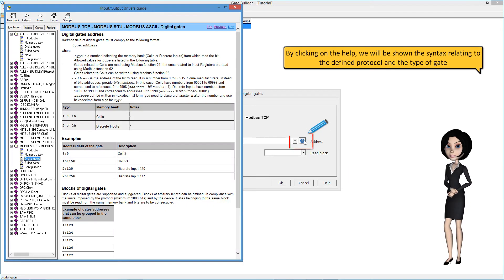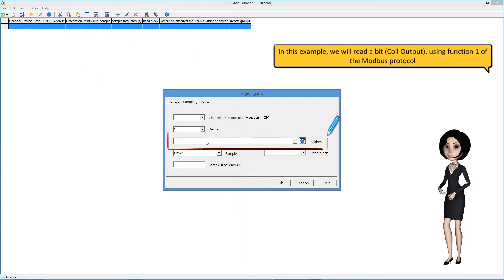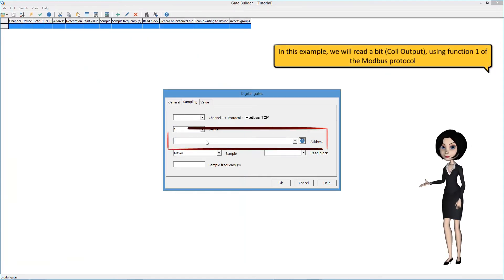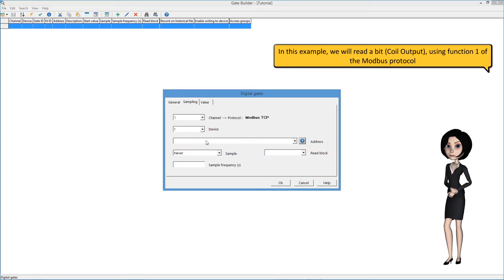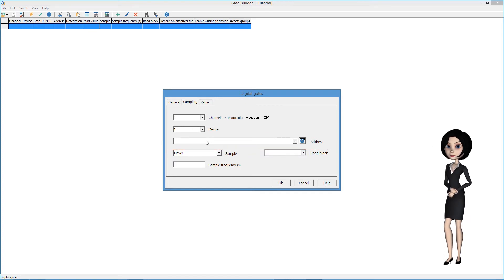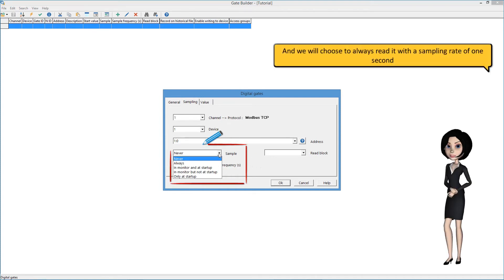By clicking on the help, we will be shown the syntax relating to the defined protocol and the type of gate. In this example, we will read a bit using function 1 of the Modbus protocol, and we will choose to always read it with a sampling rate of one second.